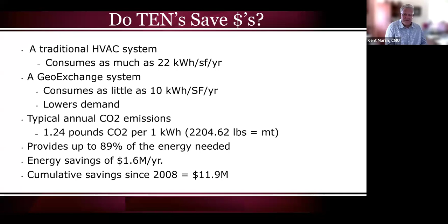The big picture numbers I use are that a traditional system consumes about 22 kilowatt hours of electricity per square foot per year, while a building served by heat pumps consumes less than half of that. That not only saves us money each year because we're buying fewer kilowatt hours from Xcel Energy, but it also greatly reduces our carbon footprint. And as Ashley's report states, it also saves us an enormous amount of processed water because we're not rejecting heat to the air through a cooling tower.